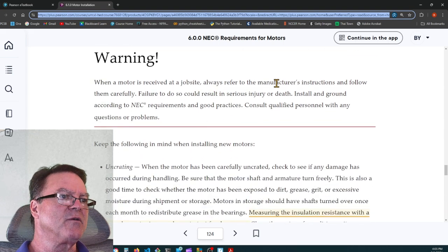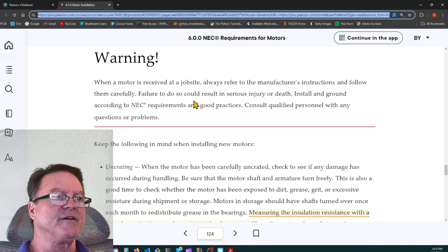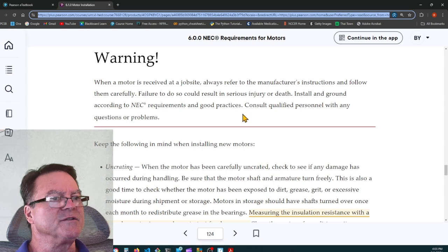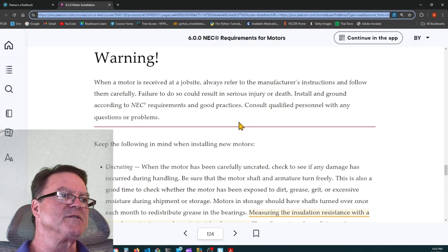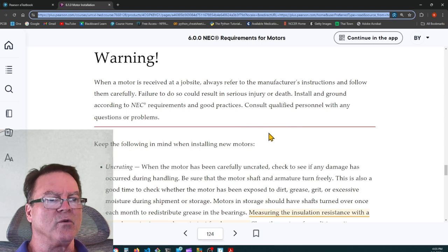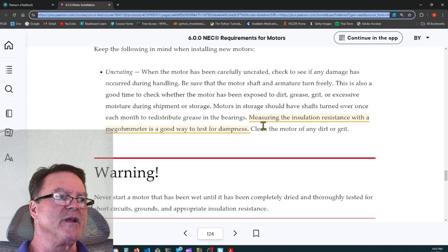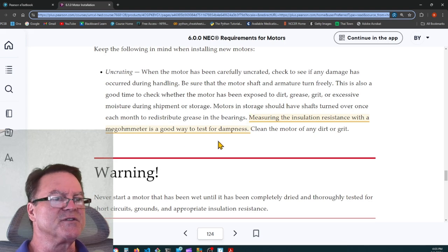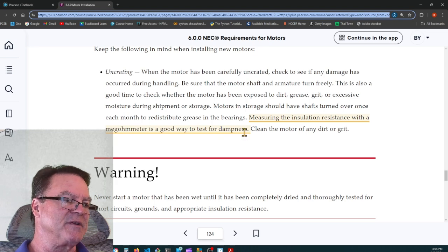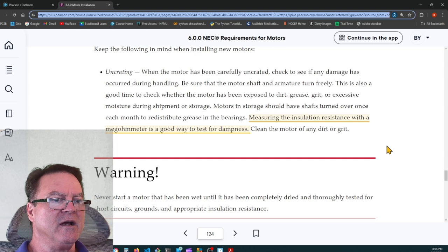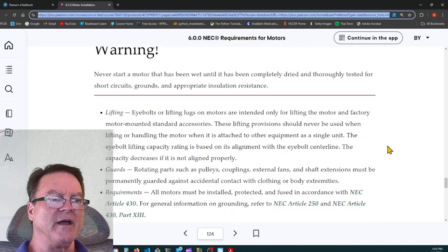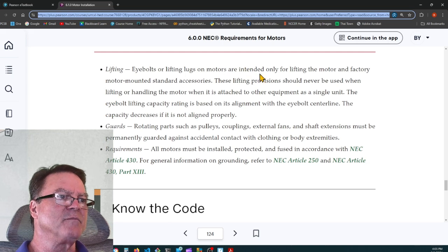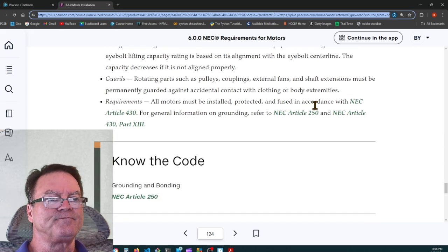All right. When a motor is received at a job site, always refer to the manufacturer's instructions and follow them carefully. Failure to do so could result in serious injury or death. Install and ground according to the NEC requirements and good practices. Consult qualified personnel with any questions or problems. Uncrating. Here's a highlight. It says measuring the insulation resistance with a megohmmeter is a good way to test for dampness. So you should have a very high measurement on that. Lifting. Eye bolts or lifting lugs on motors are intended only for lifting the motor and factory motor mounted standard accessories. These lifting provisions should never be used when lifting or handling the motor when it is attached to other equipment as a single unit.